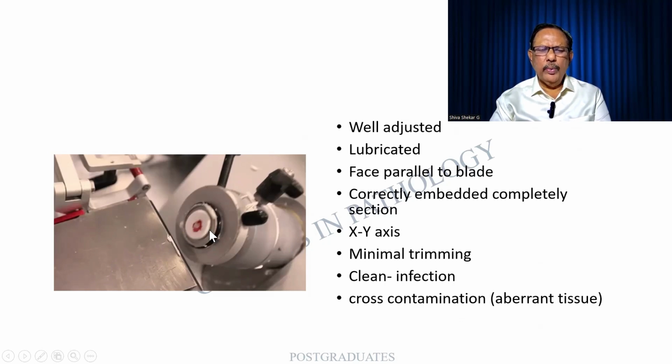So much so that when you place the block, there should be a minimal trimming because the tissue is extremely precious. And secondly, there should not be any infection or cross-contamination. Please, students, remember that this is a microtome itself. Just as in a microtome, you can have the foreign substances or tumors, etc., this also can carry it. And there are some centers where the cryostat is being used left and right. Extreme caution is needed.